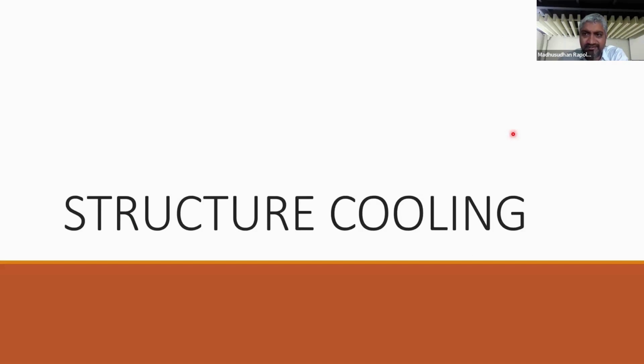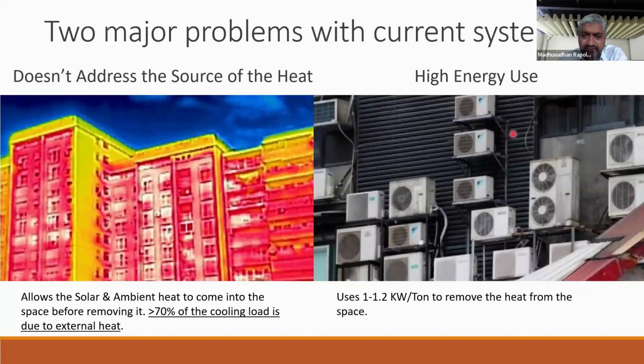The related technology is structure cooling. If you remember, in radiant cooling, we use chilled water temperature between 16 to 18 degrees centigrade to maintain 24 degrees centigrade. Now, there are spaces which don't need to be maintained at 24 degrees centigrade and are fine with 26 to 30 degrees centigrade. In which case, depending on the location, we can avoid use of a chiller or chilled water completely and use some other heat sink. And that's what we do in structure cooling, where the primary objective is to remove the heat that is being accumulated by the concrete structures.